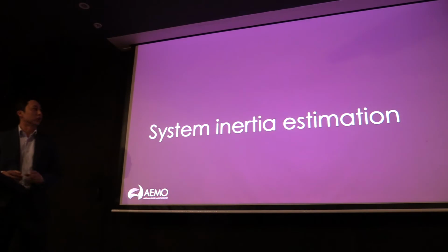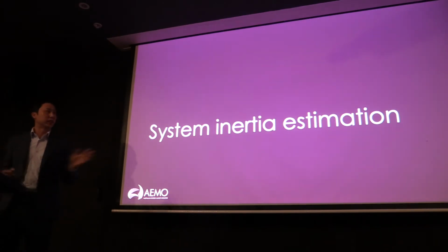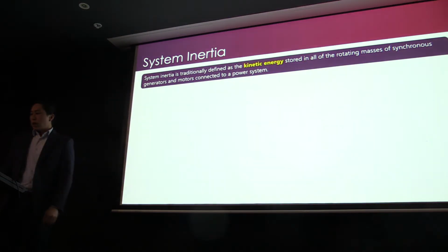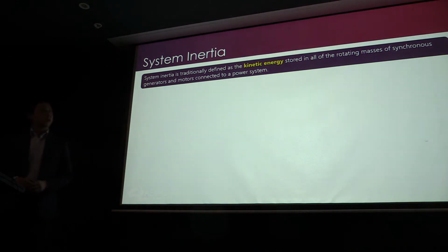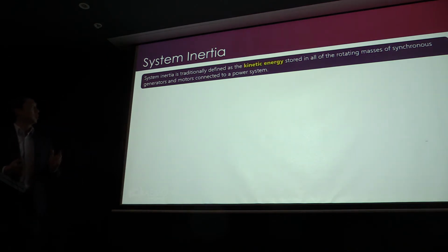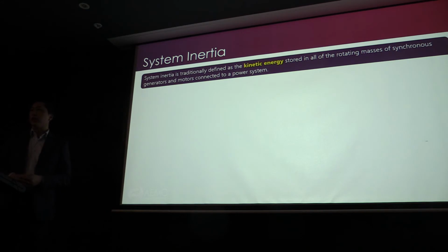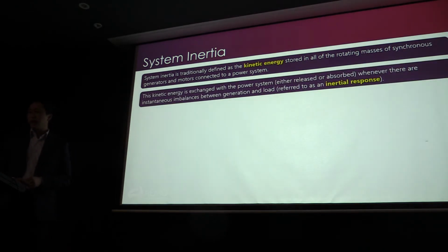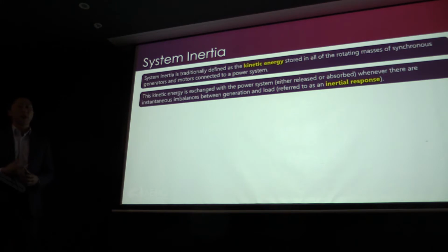So let's just get straight into system inertia estimation. Just wanted to set the scene with the SWIS. So what is system inertia to begin with? Inertia is traditionally defined as kinetic energy that's stored in all of the rotating masses of synchronous machines, both generators and motors in a power system. And it's basically energy that's exchanged with a power system.